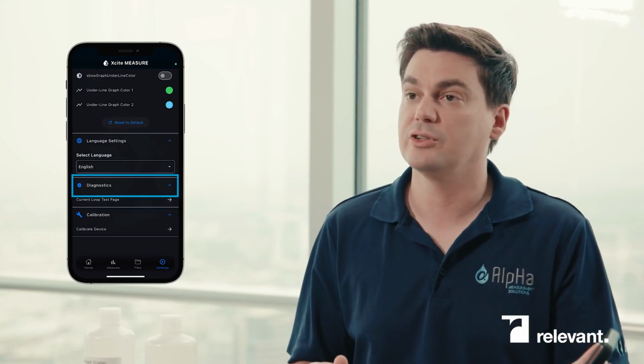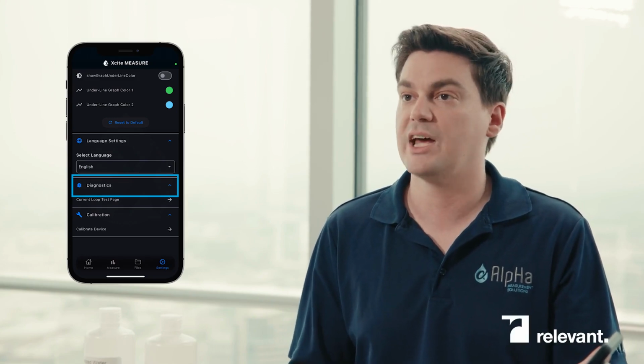With the diagnostics piece, you can current loop test your probe. Now what does that mean? The probe itself is what's known as a 4 to 20 milliamp output sensor. So what that means is the beginning of the range, the 0 in this case, is synced up to the 4 milliamps, and the top of the range, 650 in this case, is synced up to the 20 milliamps. If you want to manipulate what your 4 and 20 milliamp measurement range is, you can get into the diagnostic feature to change what that 20 milliamp is if you want to condense the range down to, let's say, 300 ppb or 400 ppb, like it's been known in the market to do.